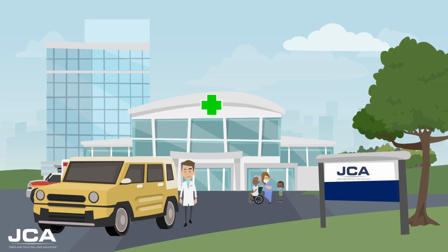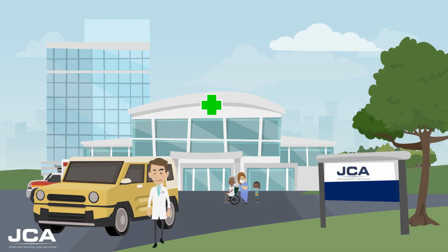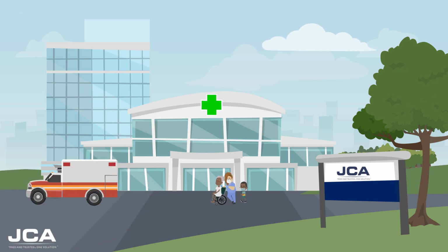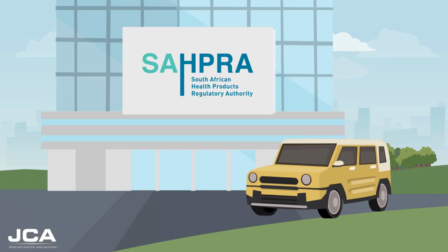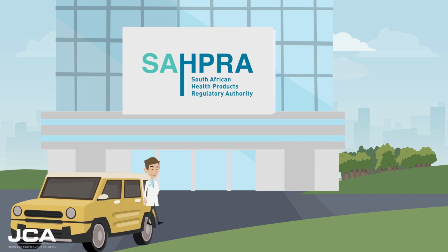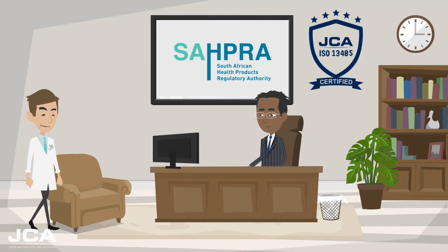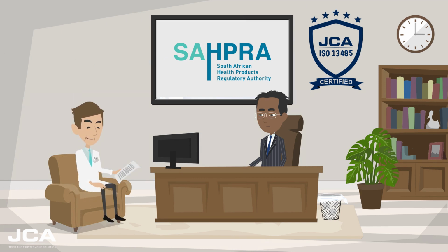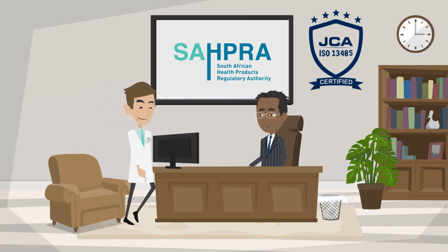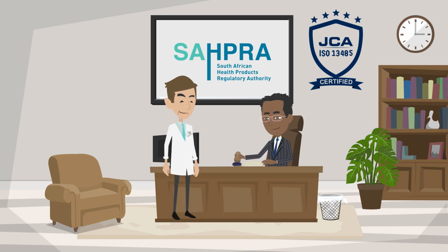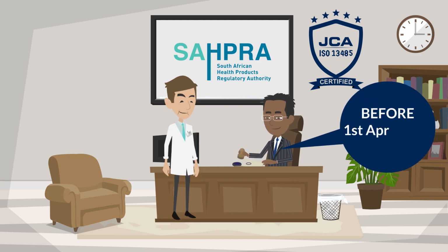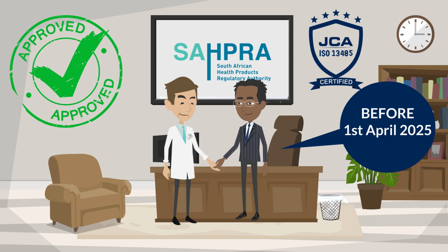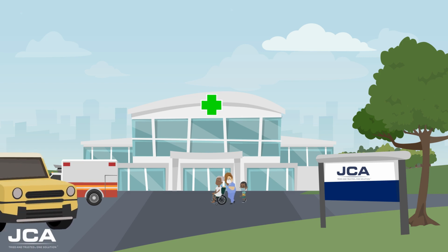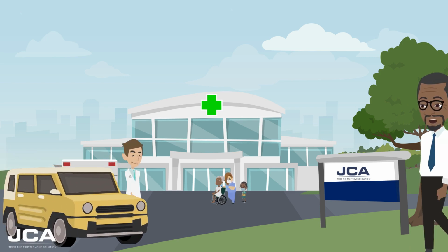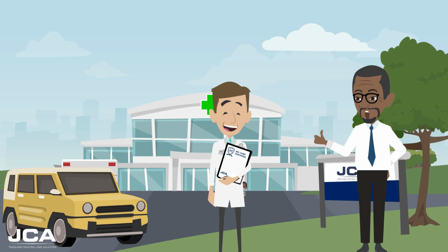ISO 13485 also requires strict adherence to regulatory requirements in the regions where your products are sold. In South Africa, SAHPRA have indicated that all companies that manufacture and distribute medical devices will be required to obtain ISO 13485 certification before April 1st, 2025 in order to apply or renew medical device licenses. One is also required to stay updated on regulations and make necessary adjustments to your processes accordingly.